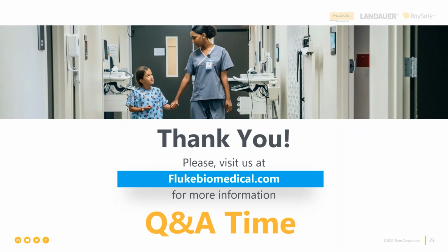So the tests that you cannot do if there's no protective earth ground testing point are: you cannot do any ground wire resistance, you cannot do any leakage current to ground, and you cannot do any applied part leakage to ground. Cannot. So those tests you will have to mark not applicable or not available because there is no ground pin. All right, there's no reference point. But even without being able to do those, you can and you must do the touch current test.